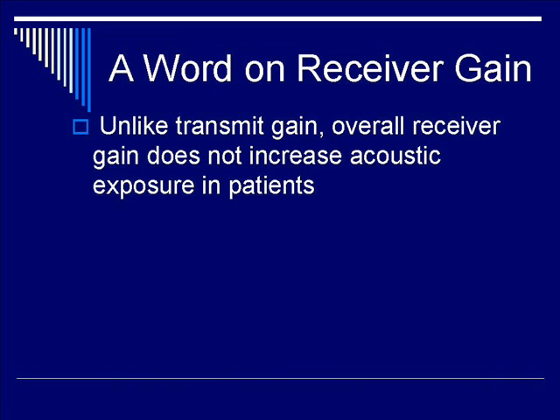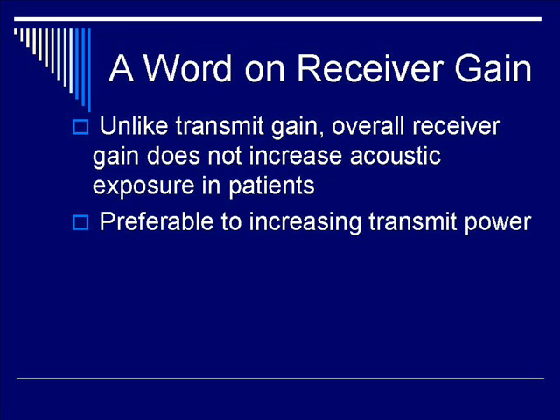A word on receiver gain: in contrast with transmitter gain, overall receiver gain does not increase acoustic exposure in patients, and therefore that's desirable. So whenever possible, it is preferable to increase the receiver gain as opposed to transmitter gain.